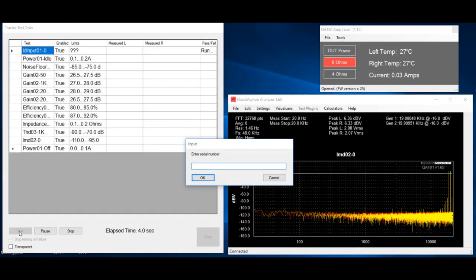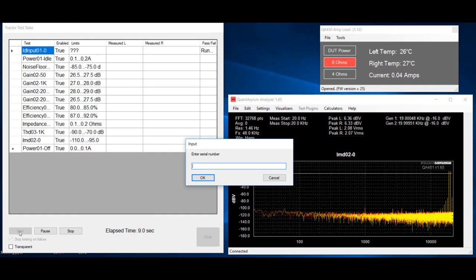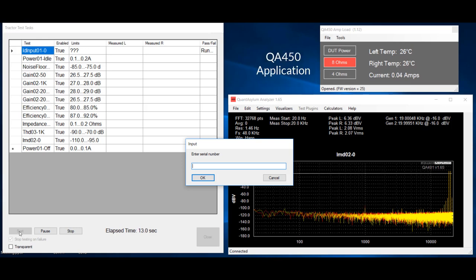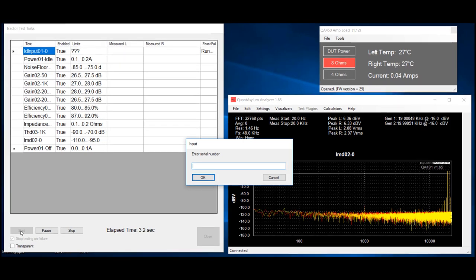Here we see the three applications open on the laptop. On the left is the Tractor application, on the lower right is the QA401 application, and on the upper right is the QA450 application. The test has been started, and it is currently paused waiting for the operator to enter the serial number of the board we are testing.